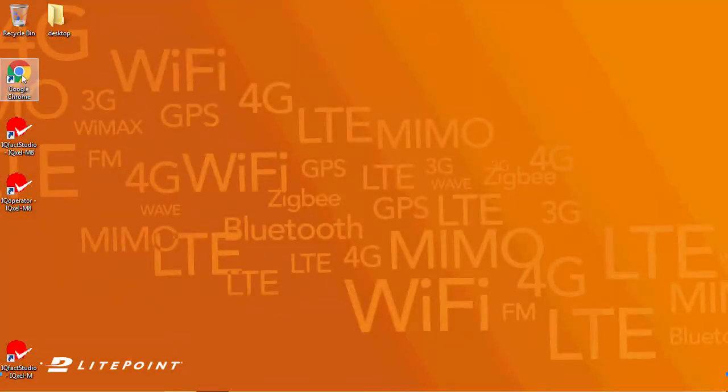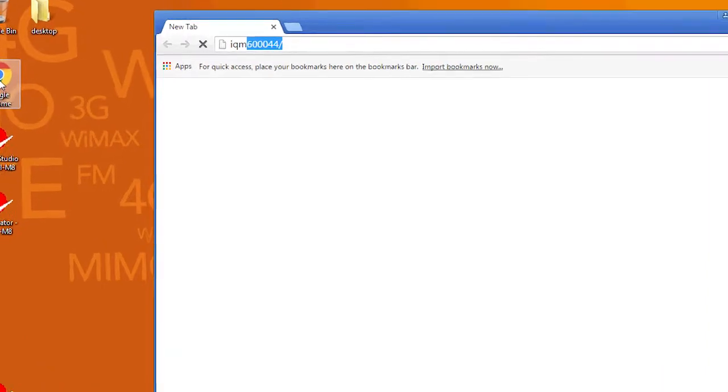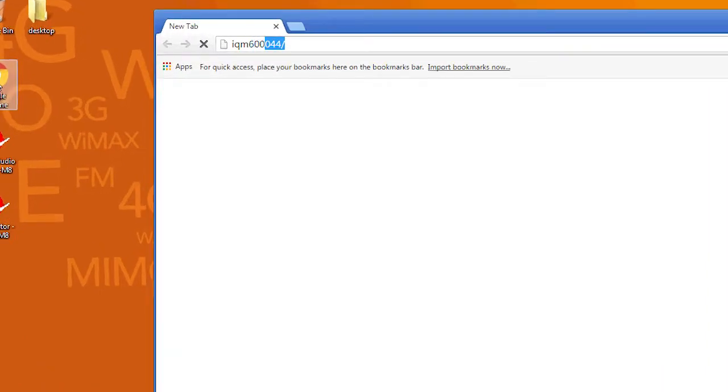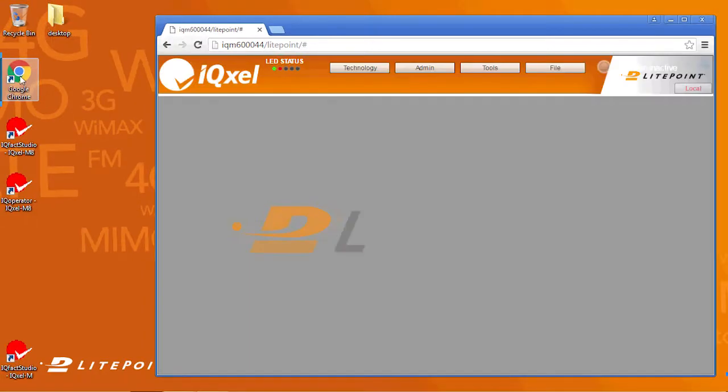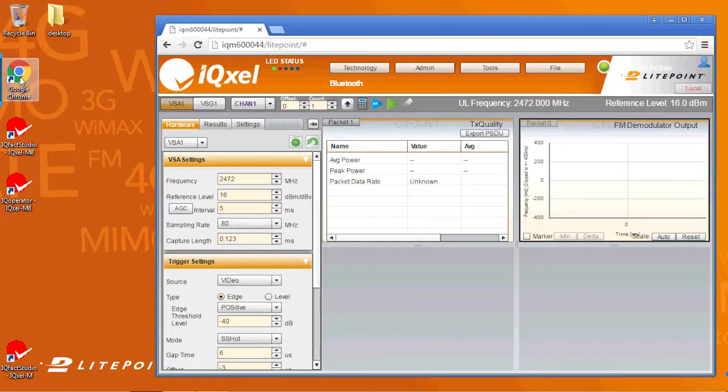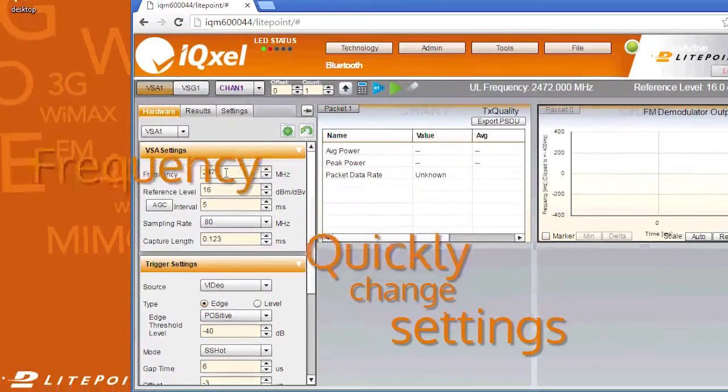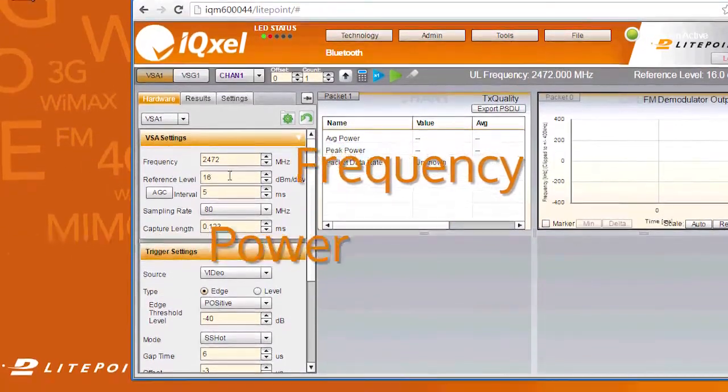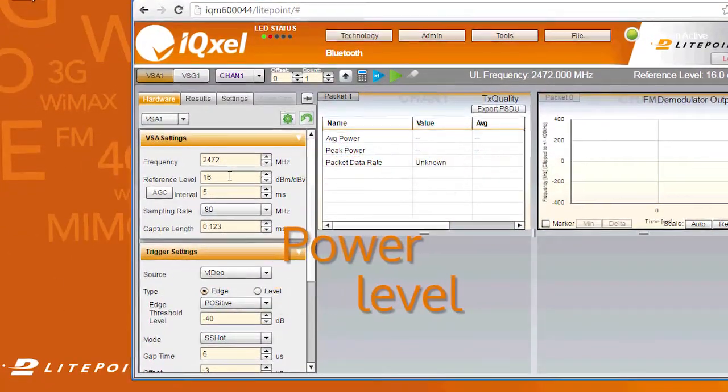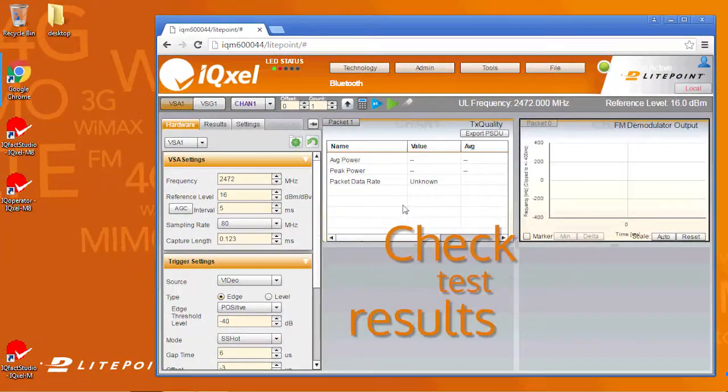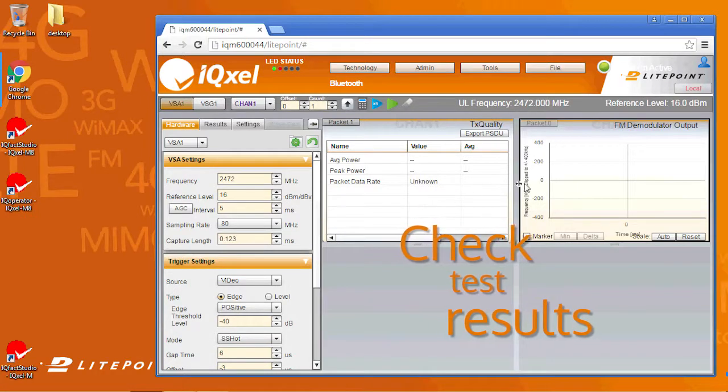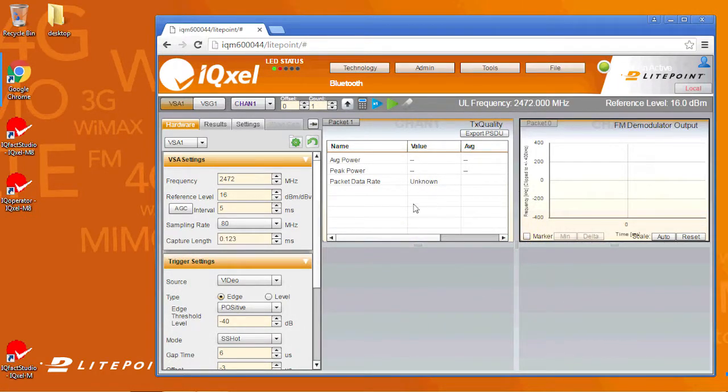Let's check the tester connection by opening the GUI. Simply type in the serial number of the tester in your browser. The GUI lets you quickly change settings, such as frequency and power level, and check test results in a tabulated format and plots.